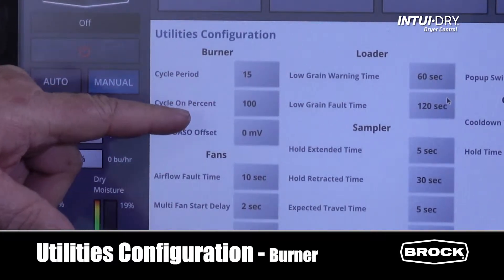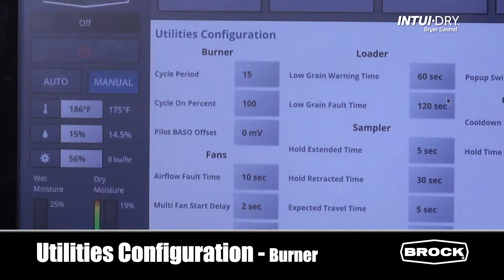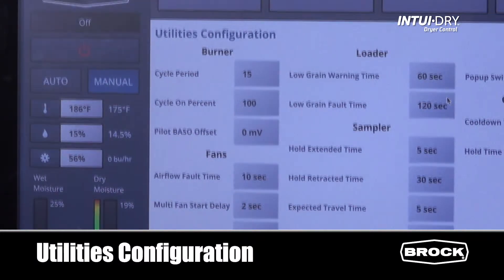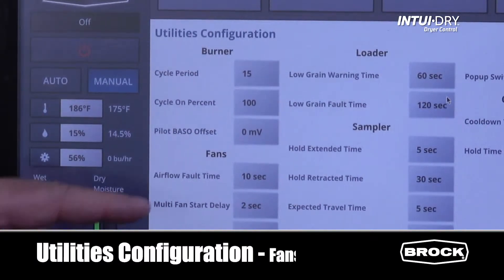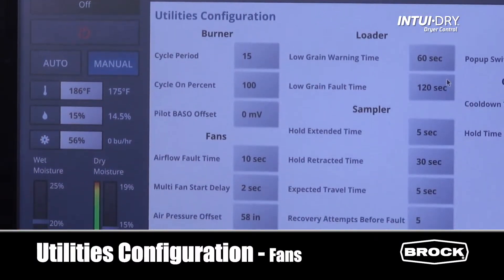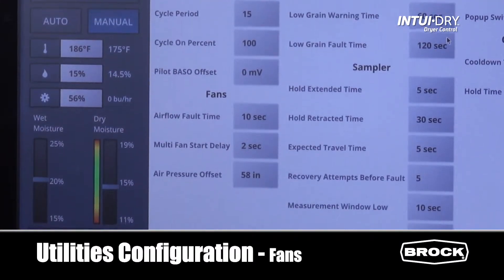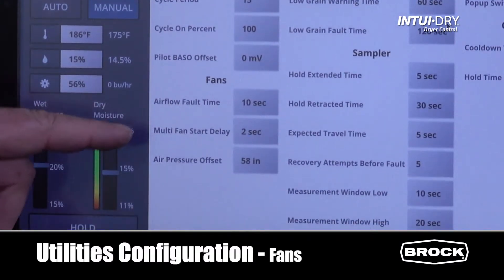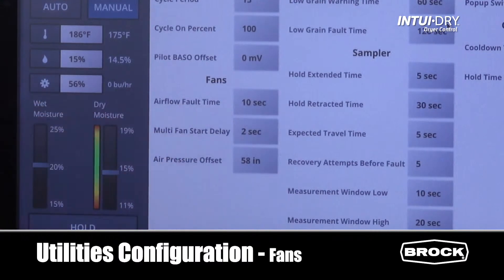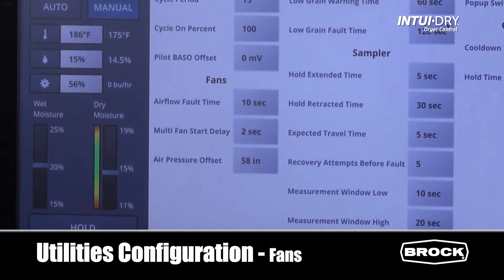On the fan airflow fault time, this is how long we wait to confirm air pressure once the fan starts. The multi-fan start delay is the time we wait between starting fan number one to fan number two, fan number two to fan number three, and so forth. The air pressure offset is also adjustable.